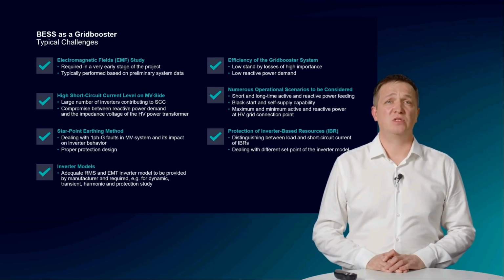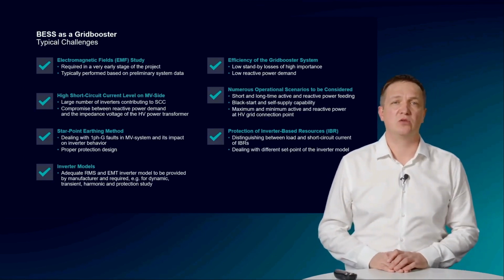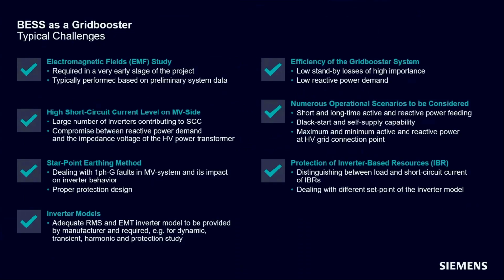Verification of the set points in an electromagnetic transient software is therefore one of the most significant milestones of a grid booster protection study. In cases where a pickup or tripping behavior of the relay is unclear, the simulation results shall be verified during hardware-based relay tests. Except from the challenges mentioned on the slide, there is a bunch of other studies required to assure proper connection and operation of the grid booster, such as harmonic, radio interference, resonance interaction, subsynchronous, torsional interaction studies.